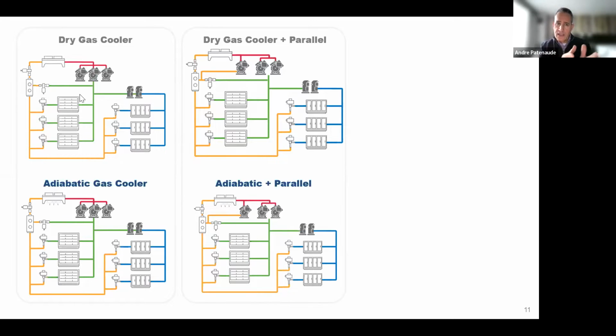You can manage the excess flash gas: instead of sending it to medium temp suction, you're sending it to an intermediate stage compressor that's operating at a much higher suction pressure. So your heat of compression is less because your compression ratios are lower. Your discharge temperatures going into the gas cooler are slightly lower. And there's an energy advantage of doing that because oftentimes you can downsize that compressor, because its capacity goes up with an increase in suction. So all that, you may find a range there of 3 to 10% energy advantage on a system by using that. Depending on where you are, it'll vary, and I'll show you some charts on that.